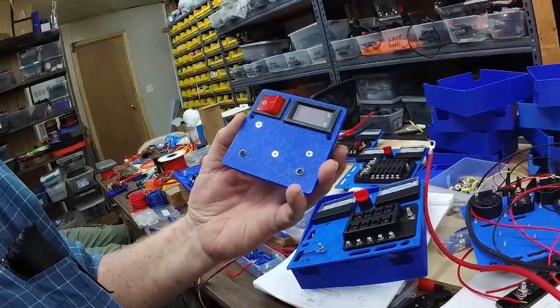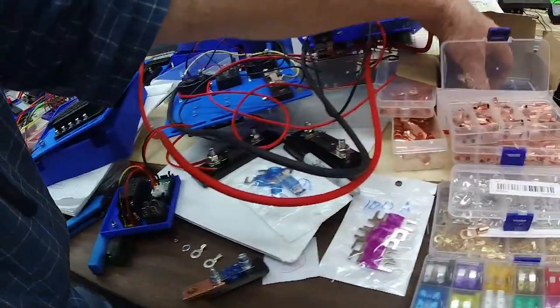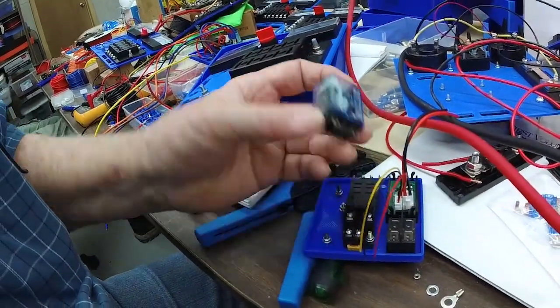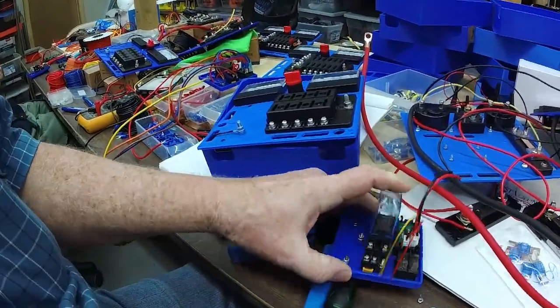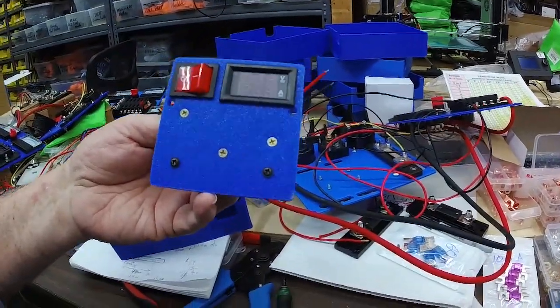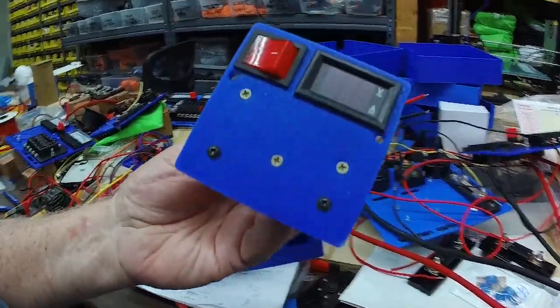Each slave panel also has a relay that can handle more than 10 amps. This relay plugs into a socket, and the relay is what switches from power supply 24 volts to battery 24 volts when there's a power failure. If you watched the previous video, you saw where we tested this out and everything works great. Each printer will need one of these little slave units wired up to it.